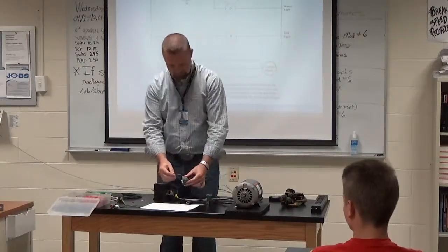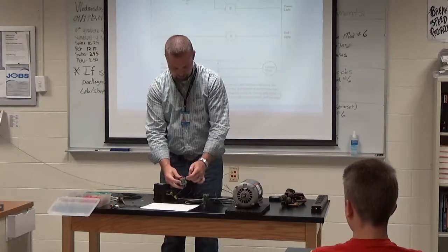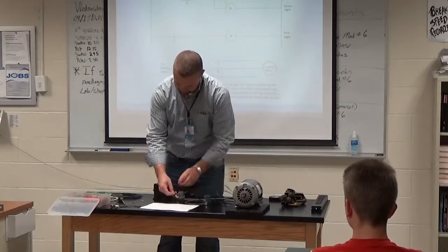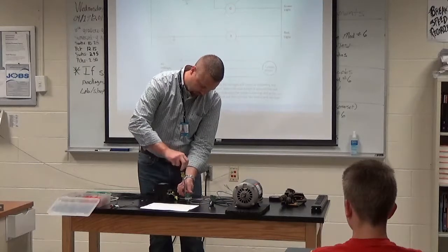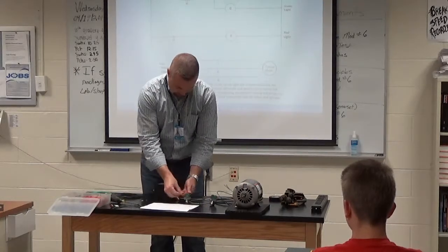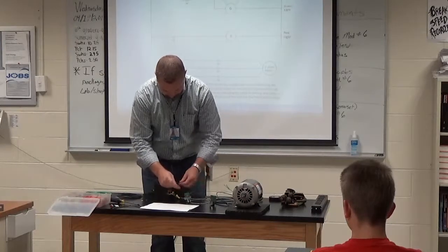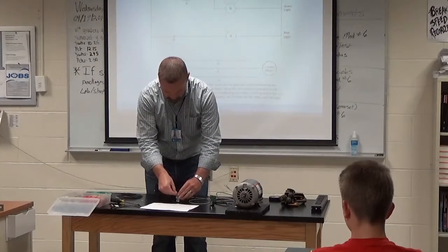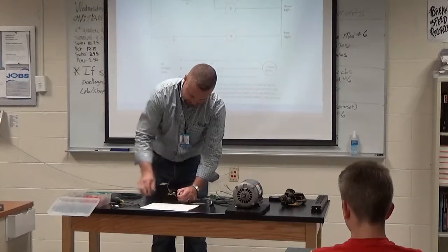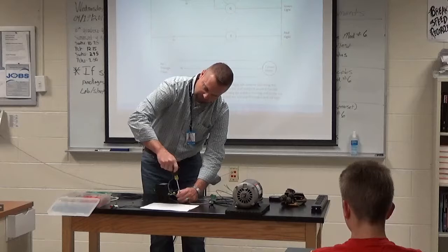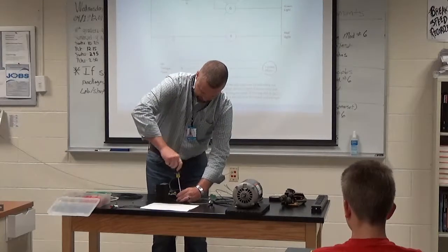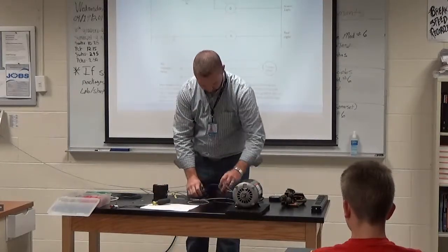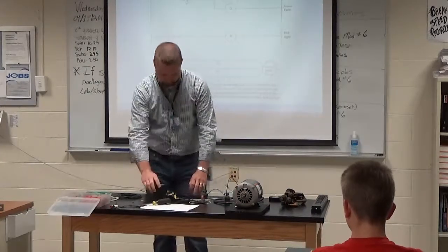Now I'm going to insert it. See guys, this is my wire, my power wire coming in my stop. This is coming out, going to my auxiliary contact. Now I must insert this wire on this side of my normally open to make that connection complete. So we're putting 2 wires under this terminal. Now, this might be a little difficult, but what you want to do is put 1 wire under one side and 1 wire under the opposite side of that screw. So when you tighten it down, the screw's in the middle between the 2 wires. You want to make sure that's secure, okay? Make sure that wire does not pop out of it. So now we have our holding circuit attached to our starter.